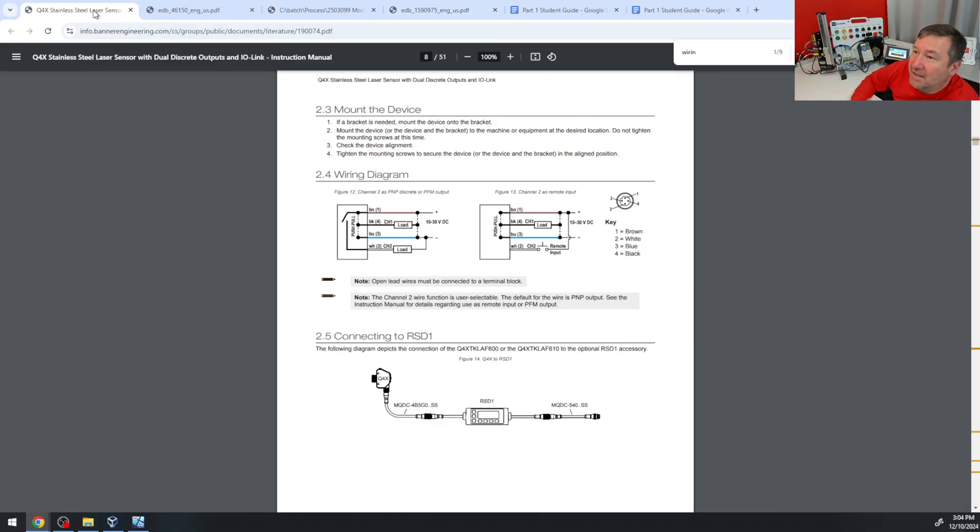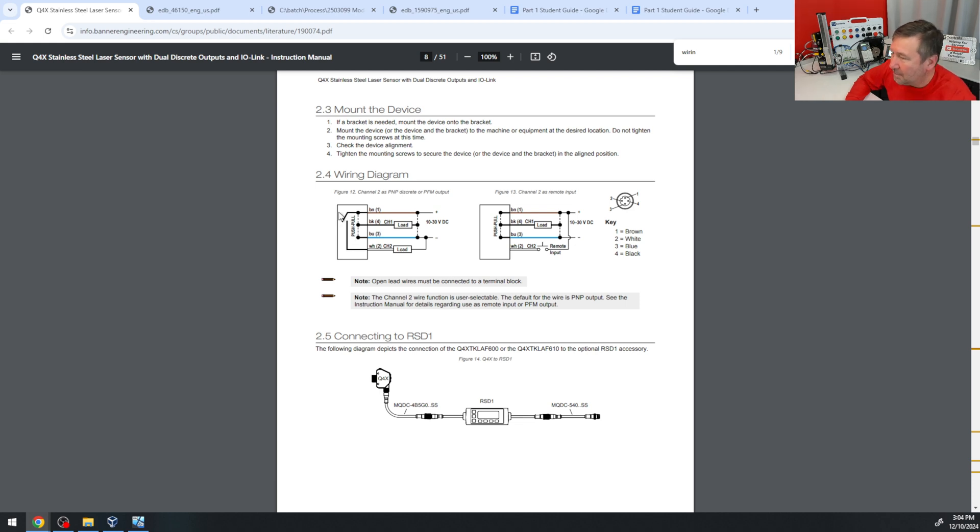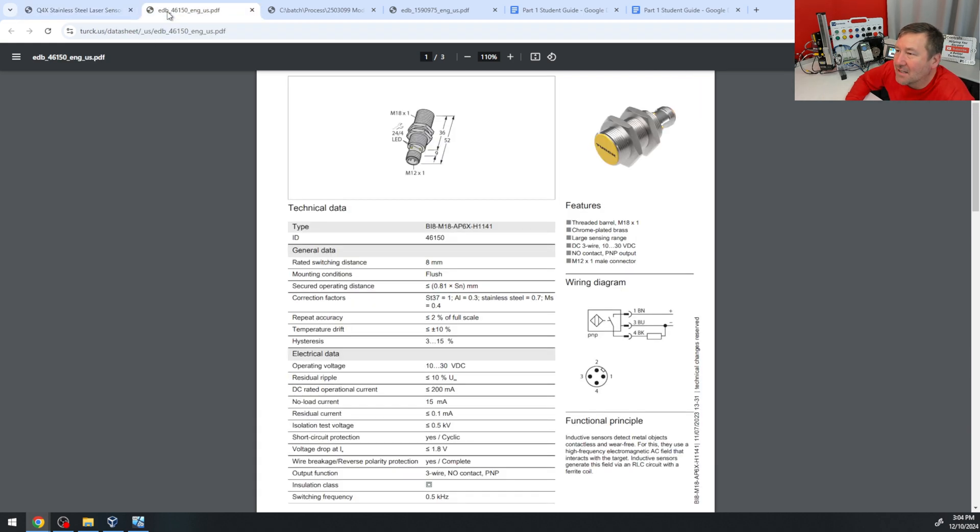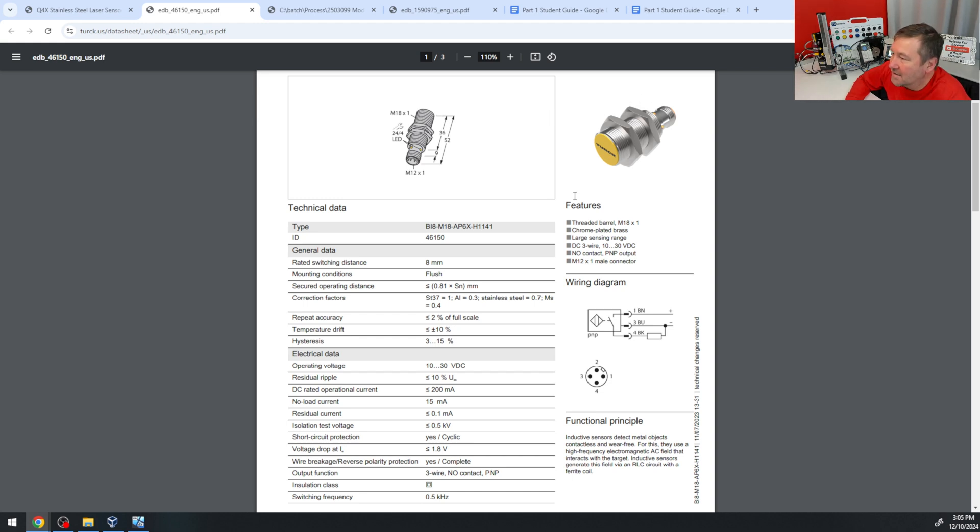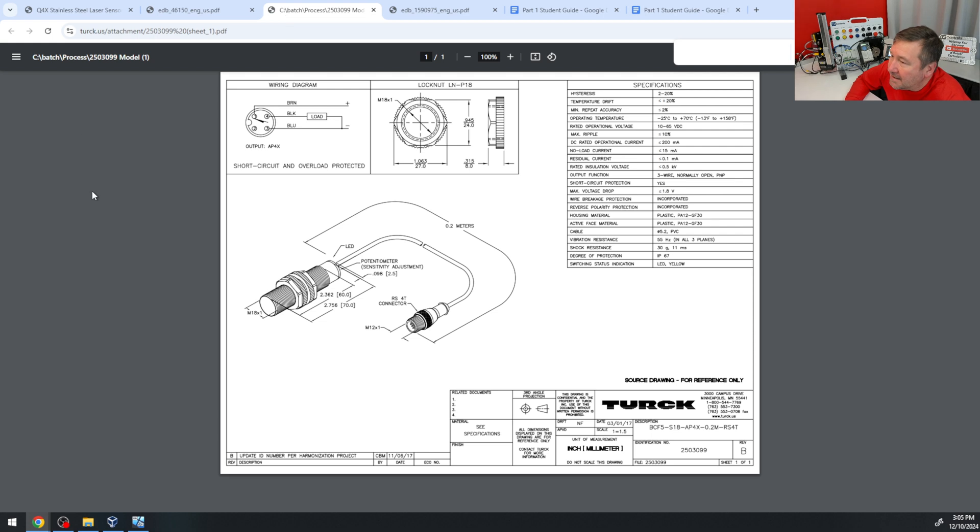So first, let's check out what our sensors are capable of. I've already downloaded the sensors, and our first one is the IO-Link sensor. Notice here, it says that it has a push-pull output. Now let's go over to our inductive prox. It says that it can be a normally open PNP output. So it is fixed one direction. And then here is our capacitive prox, and it also says it is a normally open PNP.